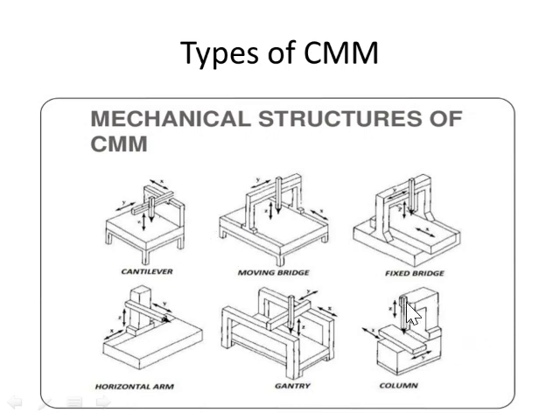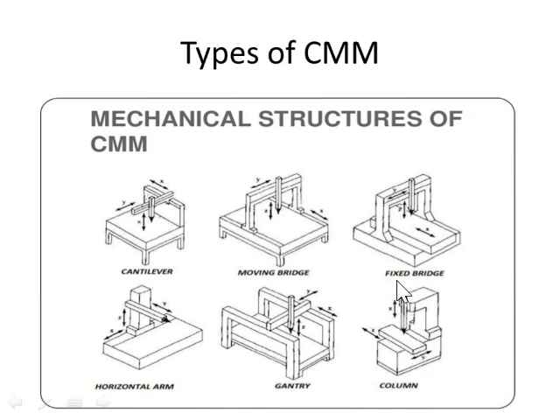The sixth type is the column type, which is quite similar to cantilever — one end fixed and another end free. But the difference is that in the column type, the bed moves in the horizontal direction, while only the probe moves in the vertical direction. In the cantilever type, both the probe and column can move in all directions. This is the major difference between cantilever and column. So those are all six types: cantilever, moving bridge, fixed bridge, horizontal arm, gantry, and column.